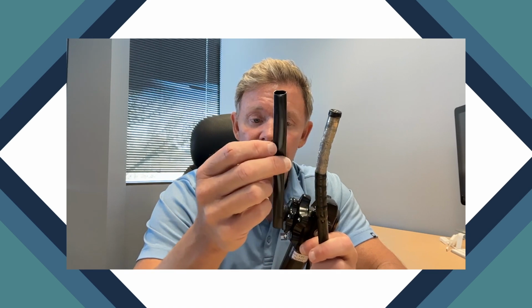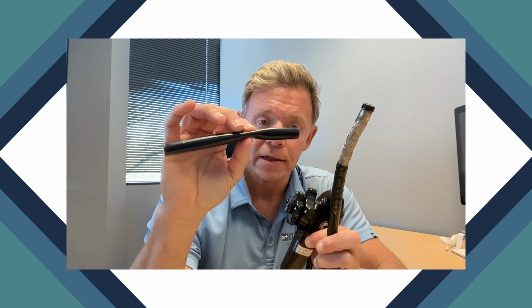I'm going to go back to the distal tip here again with you, Sherelle. When you pick up a scope in the field, I mentioned earlier that a portion of this is already taken apart. This is what we call the bending rubber. The bending rubber is a thin rubber material, and it covers the outer 5 or 6 inches of the scope. So when you pick up the scope in the field, you're not going to see the silver colored distal end here. That's going to be covered by this sheath, just like you see here. This sheath is very fragile because it's thin, and it needs to be thin because if you put something thick on the tip, it would reduce the flexibility of the distal tip. So by the design of the scope, we're stuck having to put this thin outer sheath on there. This sheath is very prone to getting cuts, nicks, holes, and leaks. So during the leak test procedure that every facility should be doing after every case, this is a common area of the scope where they will find an external leak.